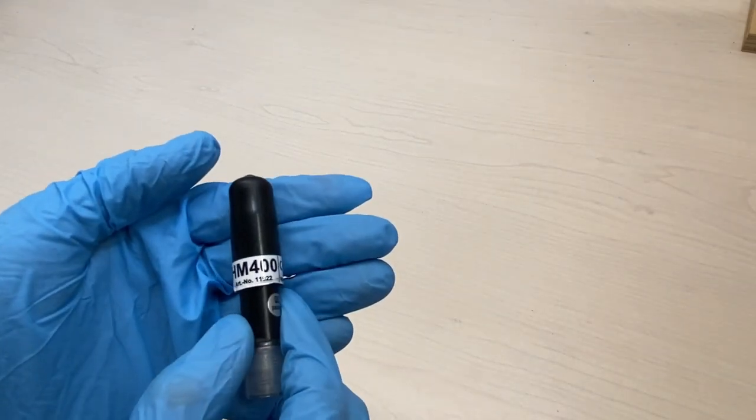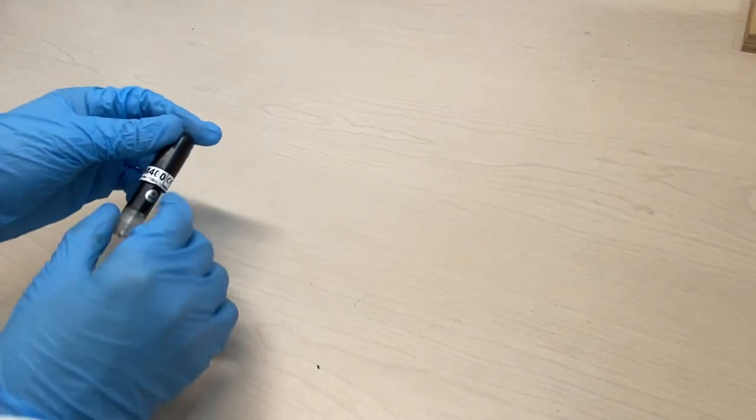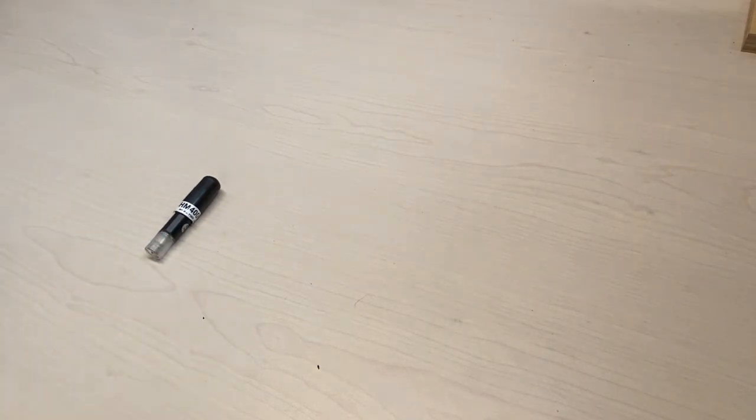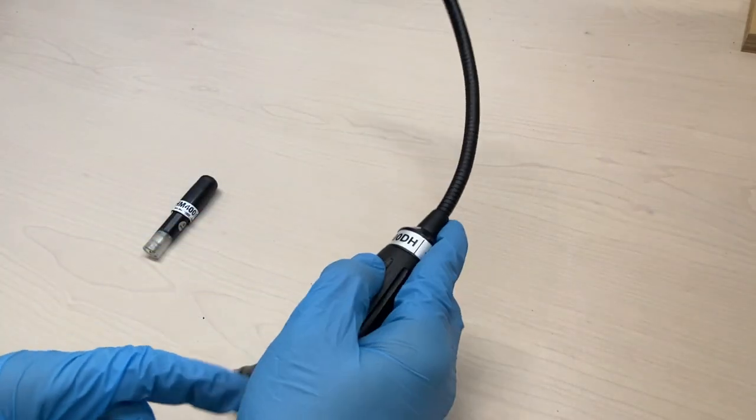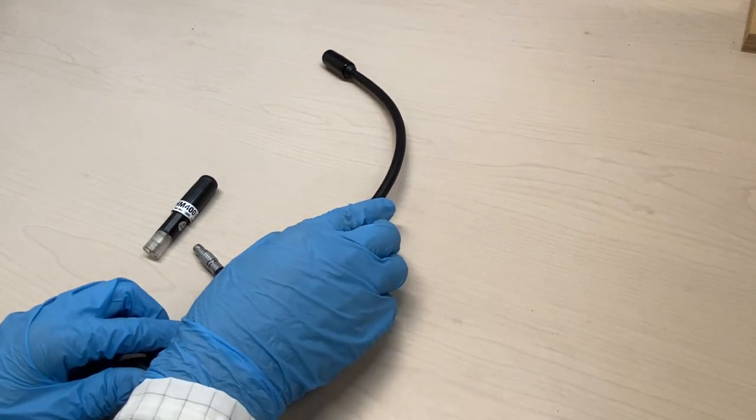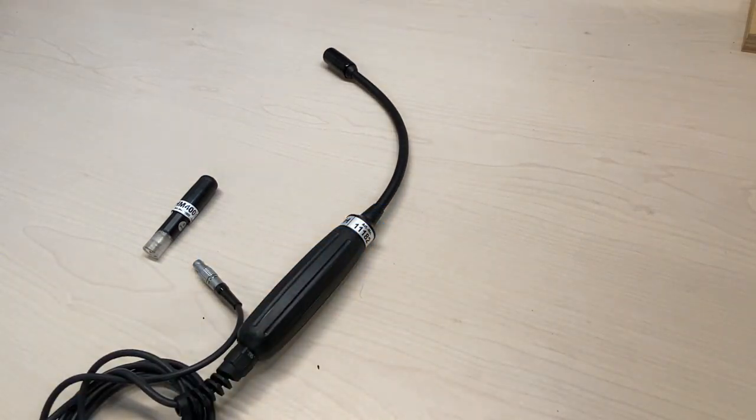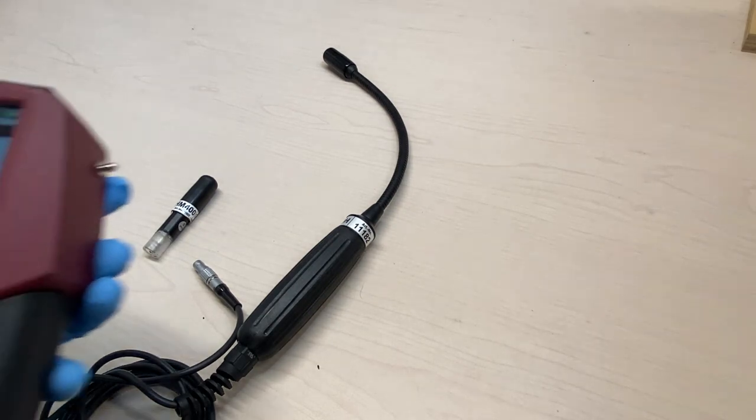Today we will explain how to use the indoor climate sensor HM400 with the Optima 7 or its newer version, the OptimaX, to determine relative humidity, temperature, dew point, and absolute pressure. After powering on the instrument, the main screen will be displayed in the window.